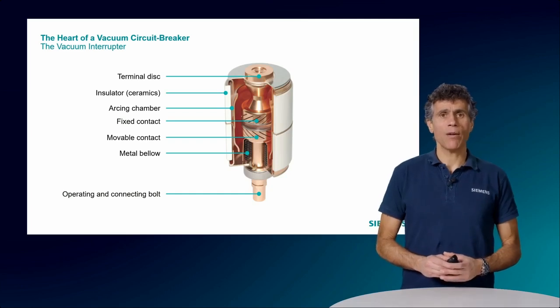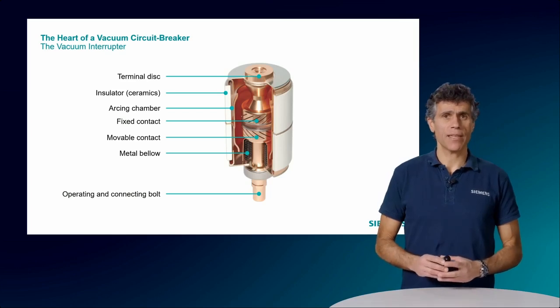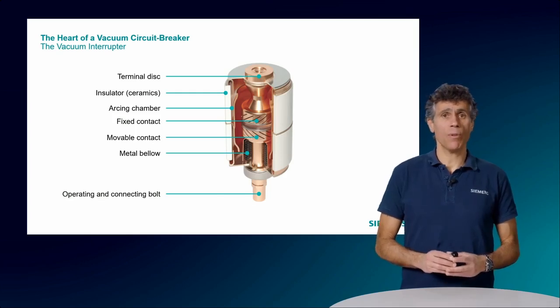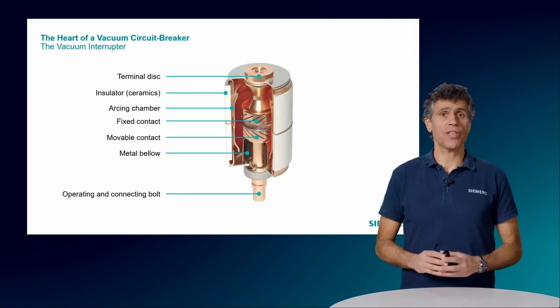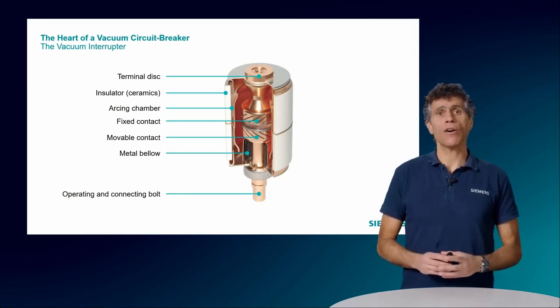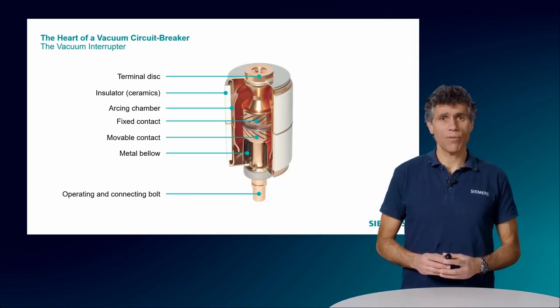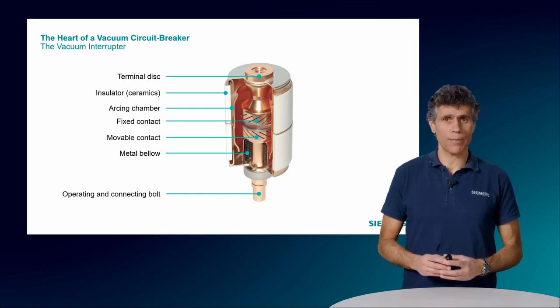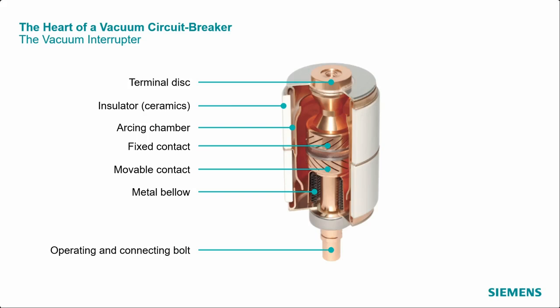The metal bellow allows the movable contact to move while it maintains the pressure and keeps the vacuum integrity inside the tube. Like the insulator, it must be able to withstand the pressure difference between the normal pressure outside and the very low pressure inside the tube. And finally, the operating and connecting bolt is a conductive bolt that is used to operate the movable contact. It connects the movable contact to the operating mechanism of the vacuum circuit breaker. When the operating mechanism is triggered, the connecting bolt either pulls the movable contact away from or pushes it towards the fixed contact to open or close the electrical circuit.